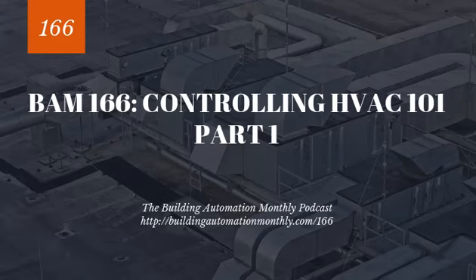You'll often hear these concepts called air changes, right? And so that is a complete change of that mass of air within that space within an hour. So you'll hear air changes in an hour, and you'll typically see in most spaces, 2 to 6 air changes an hour, depending on the occupancy level. Now, in some cases, instead of going based on space type, you can actually look at occupants, and there's a whole thing about minimum outdoor air and all that jazz. We're not going to get into that too heavily.